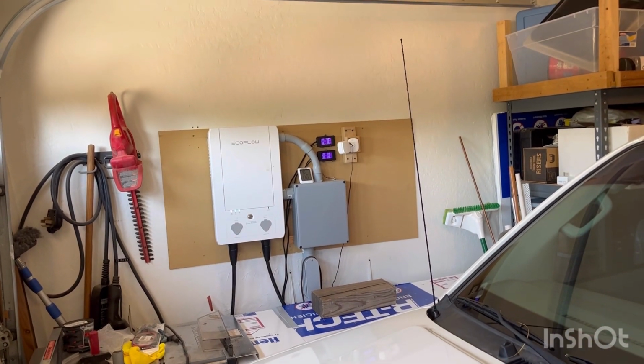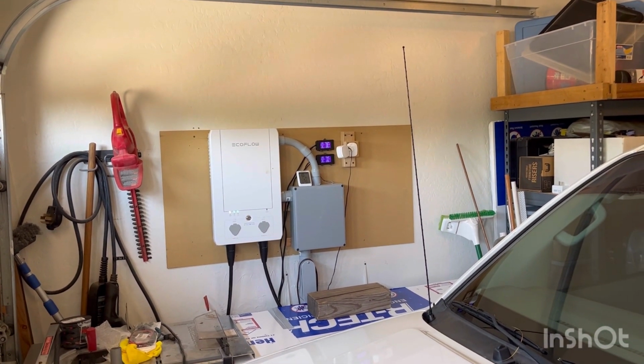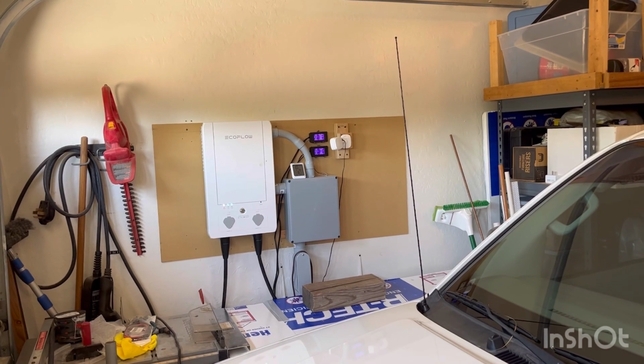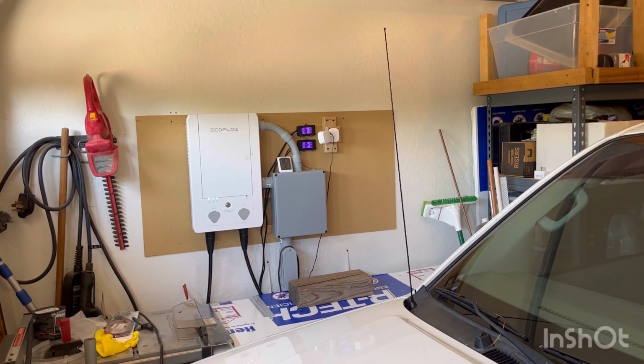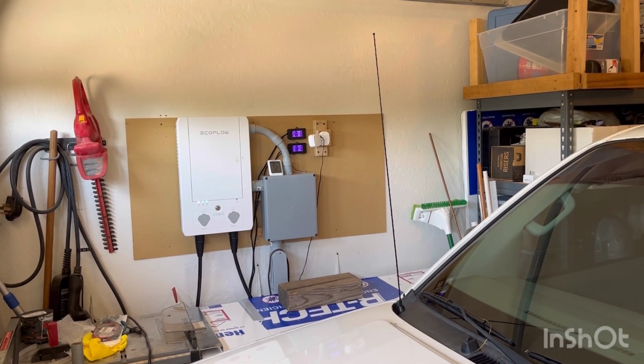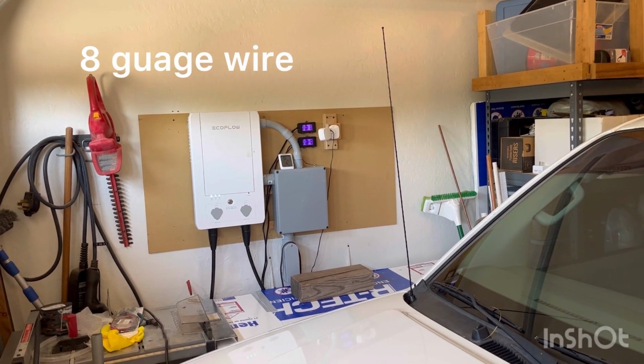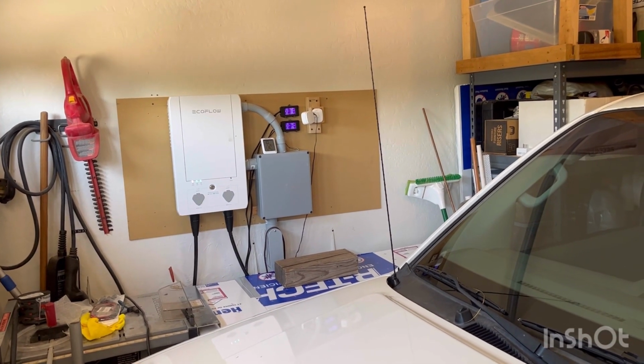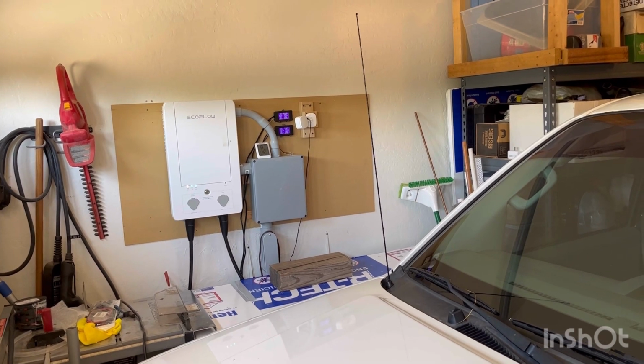If it's significant, I might have to bump down the gauge. Right now I'm running 10 gauge for 15 amp and 20 amp circuits. So the 15 amp will probably be okay, but 20 amp might require 8 gauge wire, which is pretty darn stiff and tough to work with, but you got to do what you got to do.